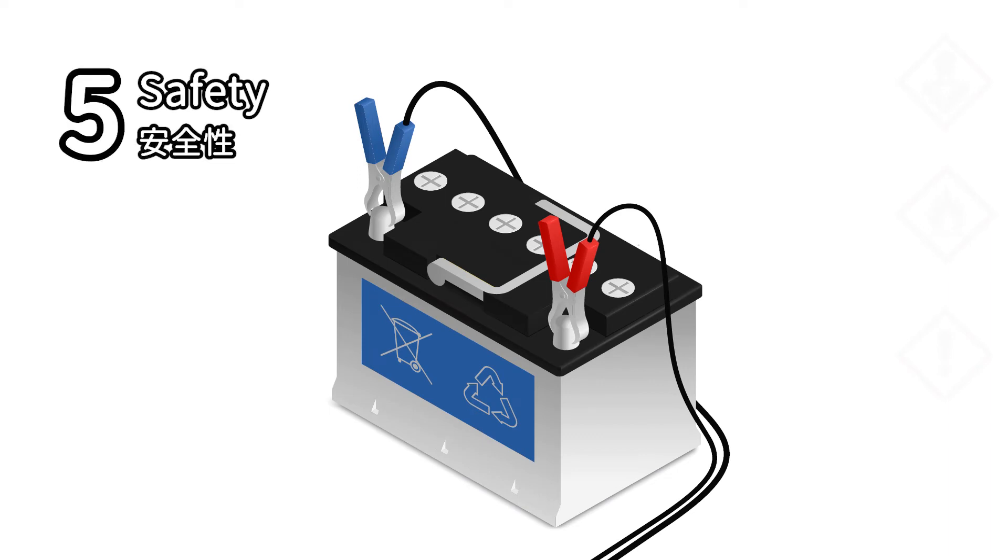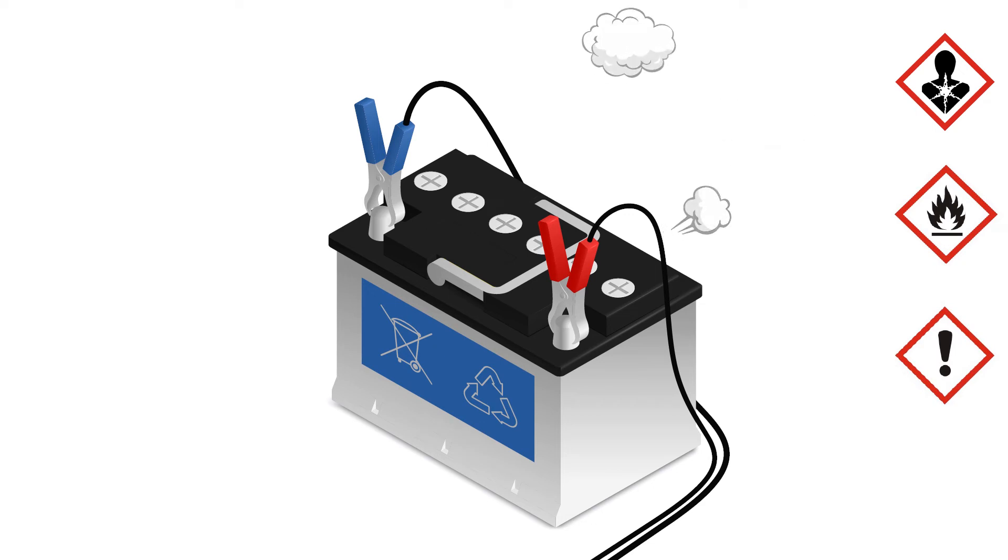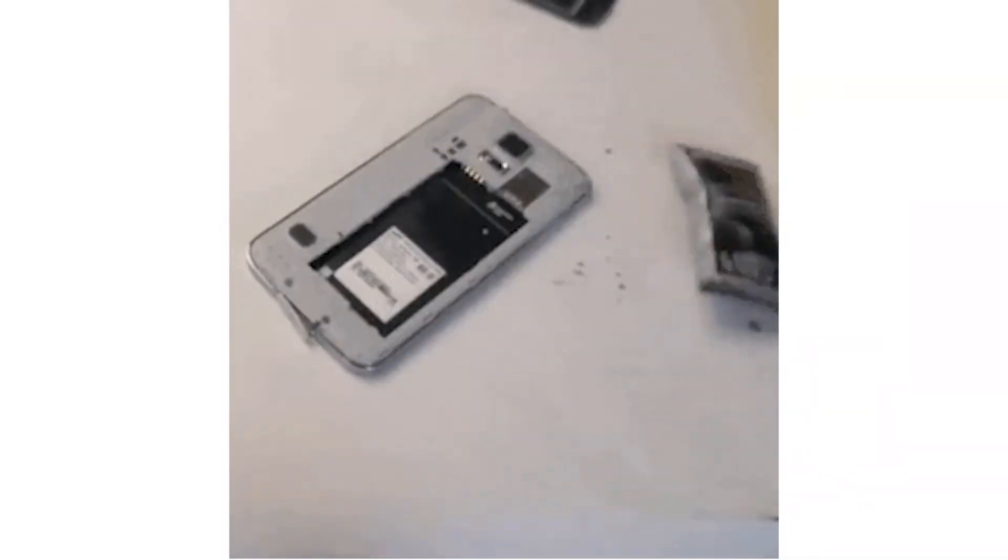5. Safety. Lead-acid batteries release sulfuric acid molecules into the air when they are charged. It irritates the respiratory tract, so there should be good ventilation when charging. Lithium-ion batteries also have high safety concerns because they contain flammable electrolytes. Damage or high temperature due to short-circuit will cause the battery to burn, or even explode in severe cases.